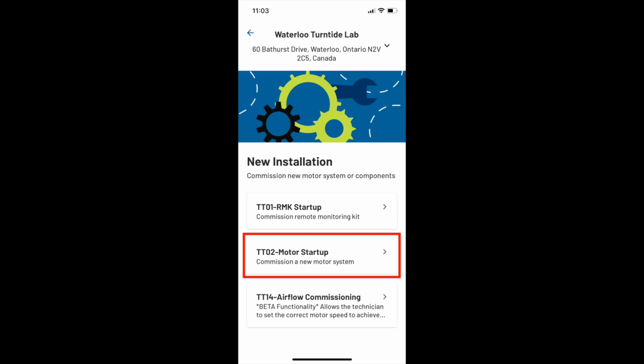The purpose of the TT02 motor startup is to commission your Turntide motor. Information captured during the TT02 will be used later to troubleshoot an installation, as well as to determine the start of the warranty period. Note that it is technically possible to commission a motor without using the TT02, but this is discouraged, as the technician app would not be able to record how or when the motor was commissioned.